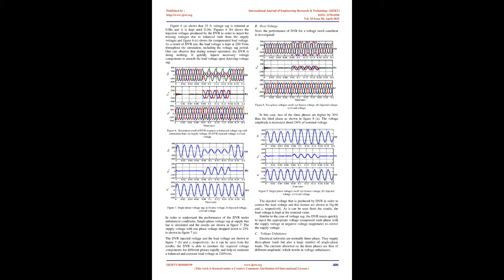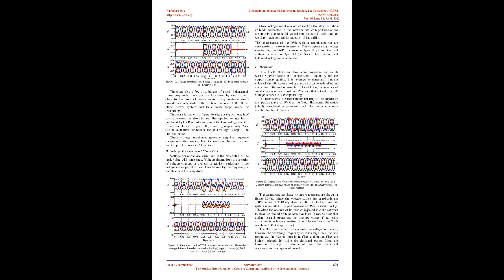For simulation, in order to understand the performance of the DVR in voltage disturbance, a simple distribution network is simulated using MATLAB/Simulink, Fig 2. A DVR is connected to the system through a series transformer with a transformation ratio of 1:1. The DVR is based on a three-phase voltage PWM inverter with an LC output filter to remove high-frequency voltage components. An RL load, R equals 10, L equals 10^-5 H, is considered. A) Voltage sags. A case of voltage sags is simulated by connecting a three-phase reactance to the busbar. The results are shown in Figure 6.